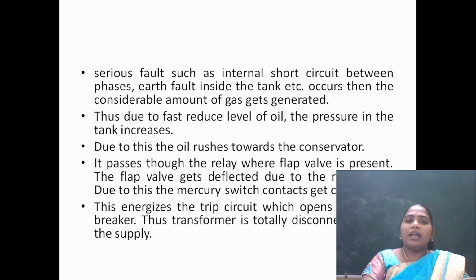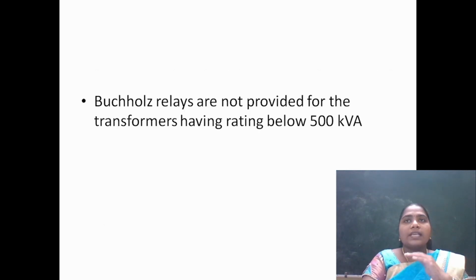Whenever a serious fault such as an internal short circuit between phases or an earth fault occurs, the amount of gas generated will be higher, and due to this the oil level reduction will be high and the pressure in the tank increases. Due to this the oil rushes towards the conservator and passes through the relay where the flap valve is present, and the flap valve is deflected by the rushing oil, and due to this the mercury switch closes the circuit contact. This energizes the trip circuit which opens the circuit breaker, and thus the transformer is totally disconnected from the supply. The Buchholz relay is not provided for transformers having a rating below 500 kVA.